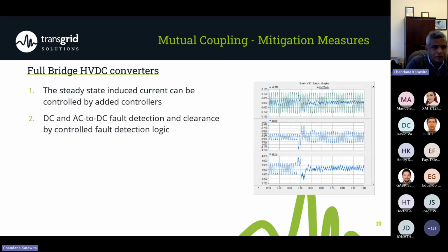And the other option is the full bridge HVDC converters. And this was the application in Ultranet actually. With full bridge HVDC converters, the converter controls can do a much better job than half bridge converters, because with a full bridge HVDC converter, you can control AC and DC independently. So you can use this capability to control the induced currents, as well as to detect the AC to DC faults and clear them using controlled fault detection logic. So we evaluated this for Ultranet and showed that this is feasible. So right now Siemens is implementing these controllers into Ultranet.